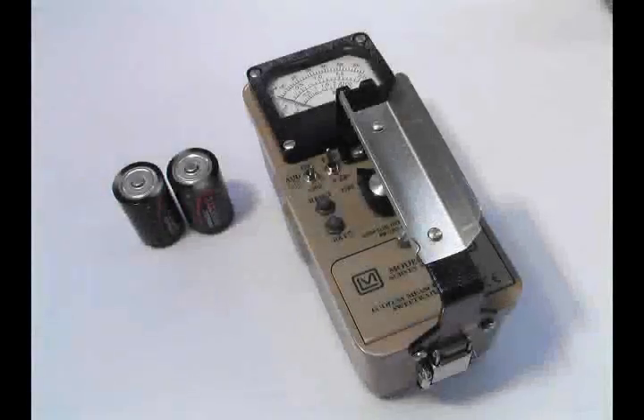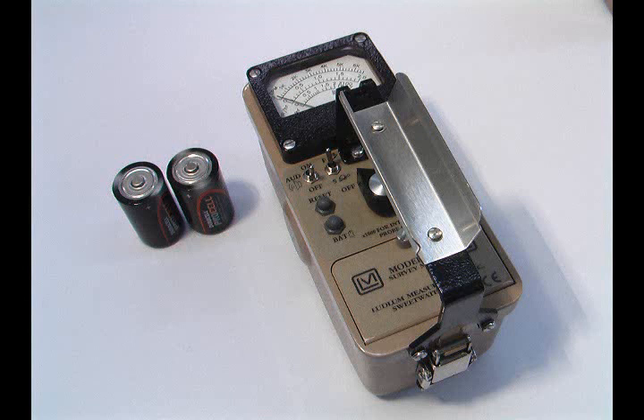The Model 14C operates on 2 D-cell batteries with a typical battery life of 2,000 hours. Change the batteries as soon as possible when the battery voltage becomes low. The Unimorph speaker will emit a continuous audible tone to warn of imminent battery failure. For extreme cold environments, very fresh alkaline or rechargeable nickel-cadmium batteries are recommended. Remove the batteries if the instrument is to be stored greater than 30 days.